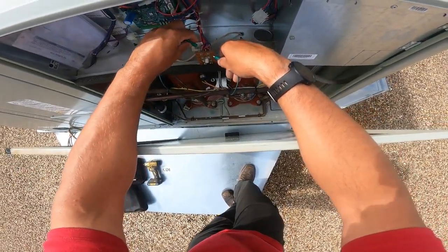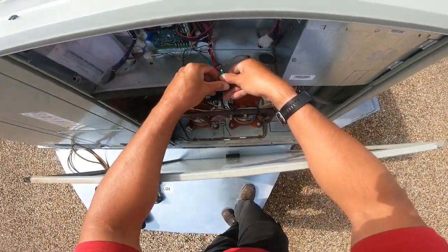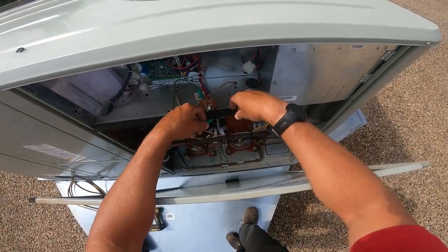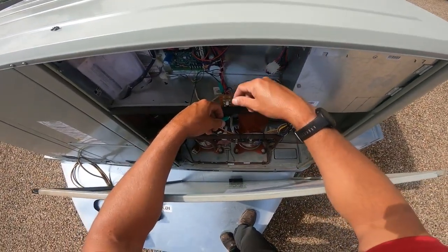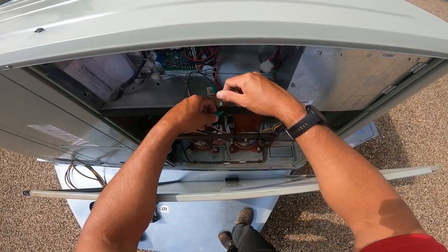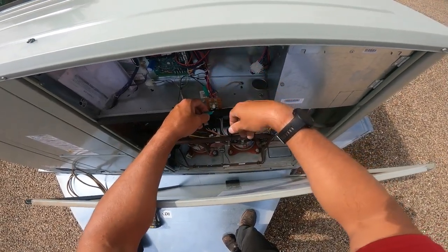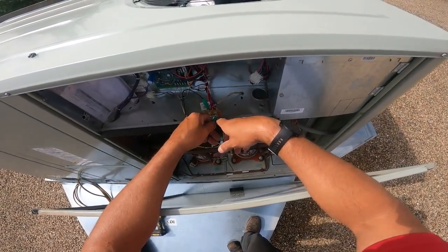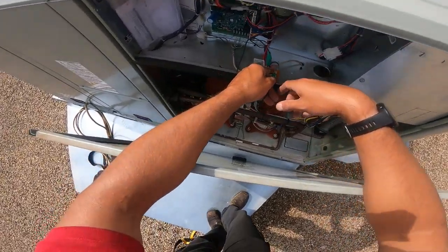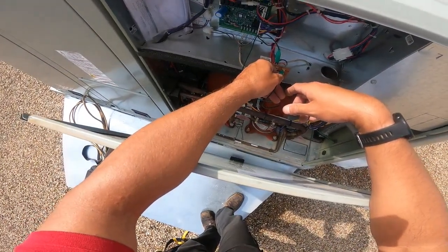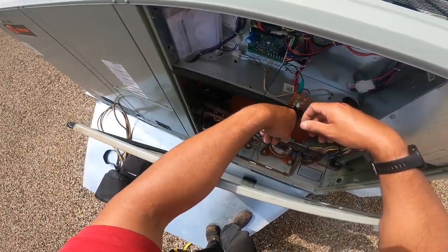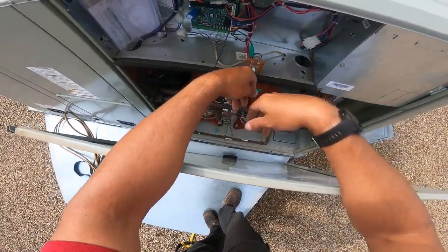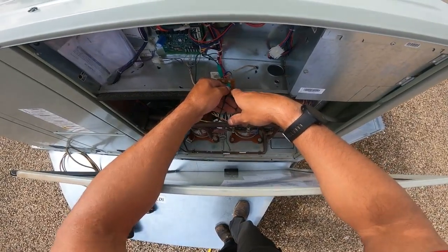So what I like to do, let me just go ahead and hook this on. So you're going to hold it for 3 seconds, let it go for 3 seconds, then hold it for 3 seconds and let it go for 3 seconds until you get to whatever you're trying to test on. So the first one should be the economizer, so I'm going to go hold. Oh, first one's blower. Alright, then this light here will blink like a heartbeat, so you know that it's in test mode. I'm gonna go hold.